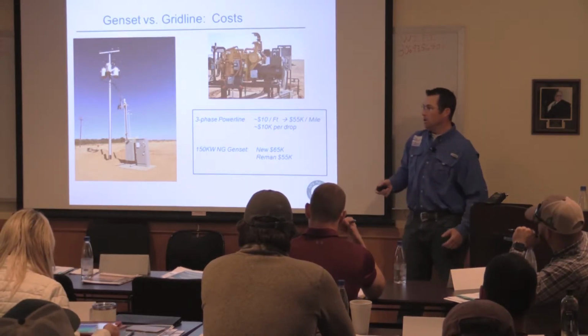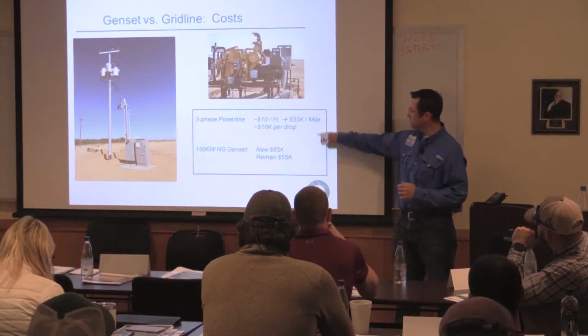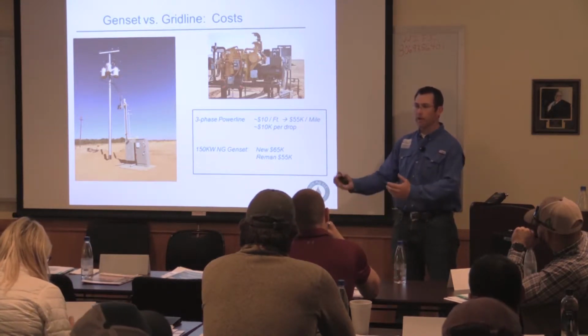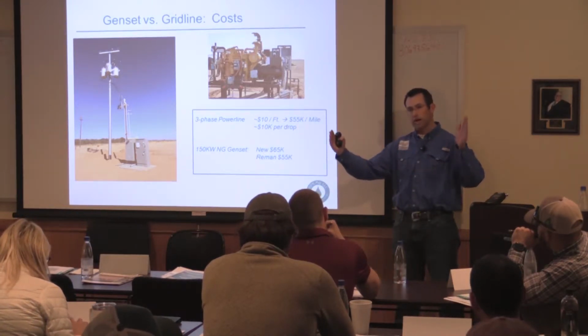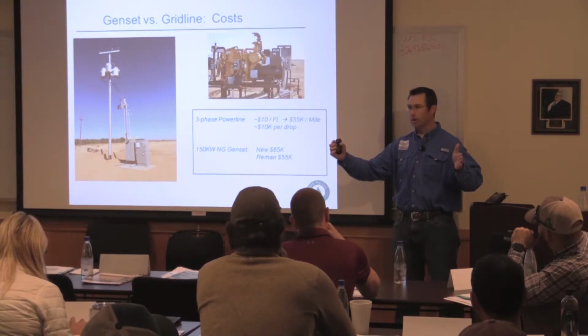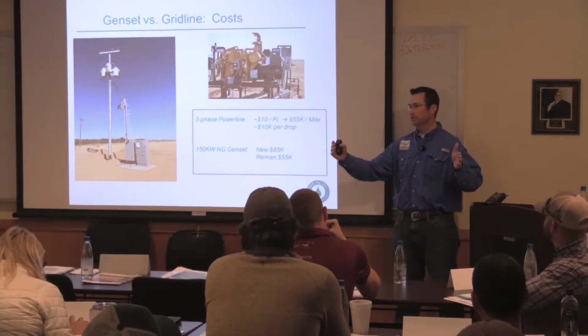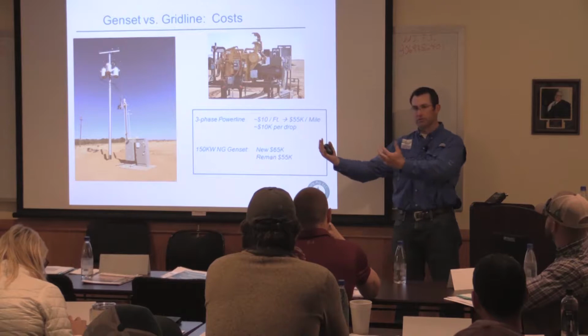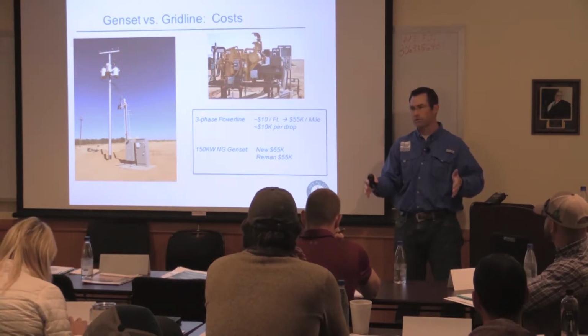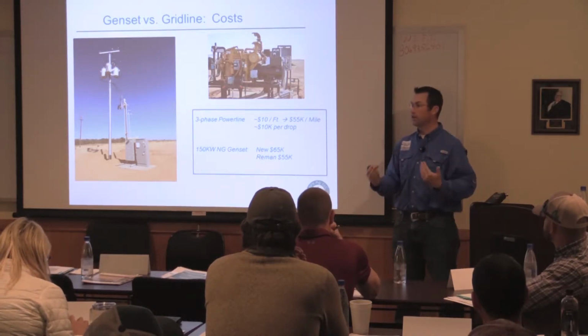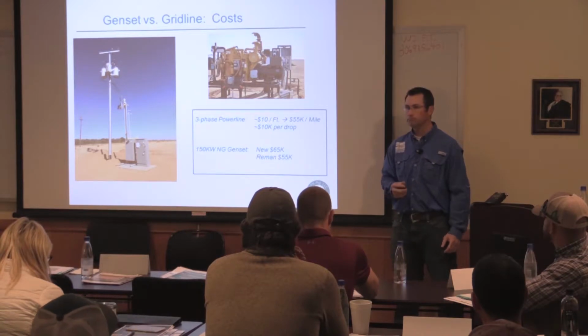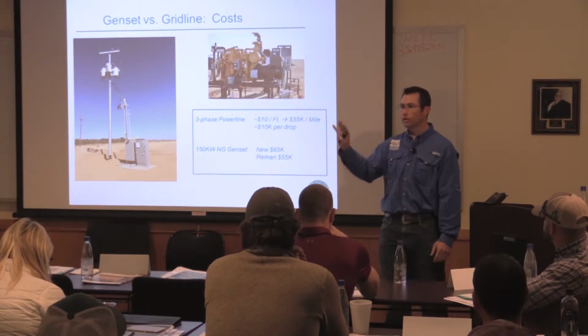Okay? The reason I put these up here, because they're so close, is that if you are looking at bringing new power in, if you have to run line a mile, it's basically going to be a wash in your cost of that capital expense. Setting up the genset versus bringing in the power line is going to be a wash. And then you can start to compare it on the unit and the margin. We good to this point?